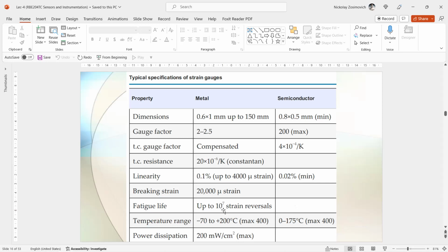In this table, we list some specifications of strain gauges. For comparison, a column for the user-mountable semiconductor strain gauges has been added. It should be noted that these gauges show a considerable nonlinearity. It means that even in a balancing bridge, this effect cannot be neglected. And typically, standardized resistance values of strain gauges are 120, 350, 700, and 1000 ohms.